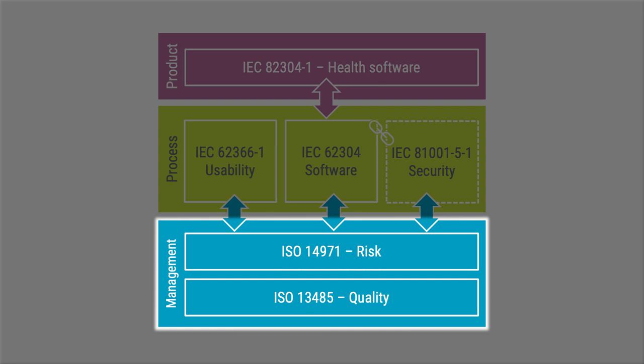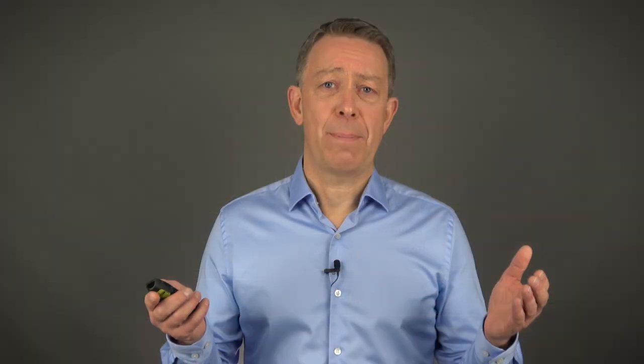ISO 14971 contains requirements on your risk management process — that is, how you should be performing risk management. The risk management process provides one of the most important inputs to a software development process: hazardous situations. A good understanding of a hazardous situation is key to performing meaningful software risk management and getting it right. You can find courses on both ISO 13485 and ISO 14971 on Medical Device HQ.